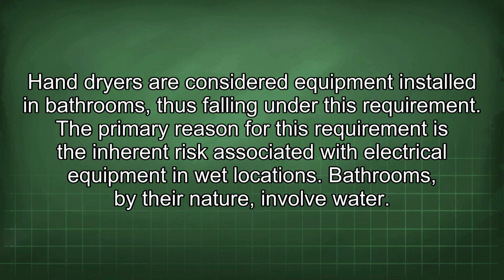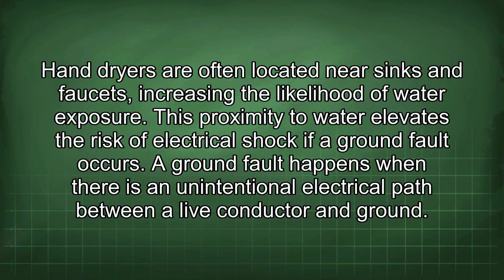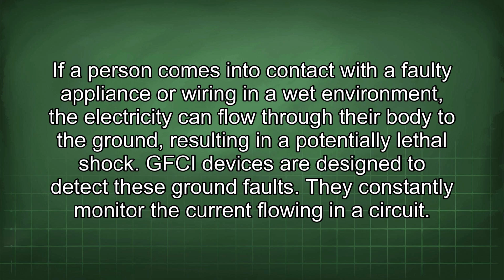The primary reason for this requirement is the inherent risk associated with electrical equipment in wet locations. Bathrooms, by their nature, involve water. Hand dryers are often located near sinks and faucets, increasing the likelihood of water exposure. This proximity to water elevates the risk of electrical shock if a ground fault occurs. A ground fault happens when there is an unintentional electrical path between a live conductor and ground. If a person comes into contact with a faulty appliance or wiring in a wet environment, the electricity can flow through their body to the ground, resulting in a potentially lethal shock.